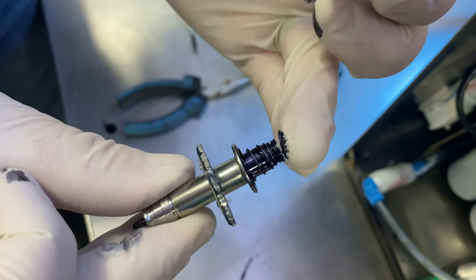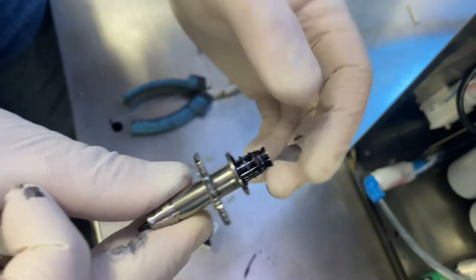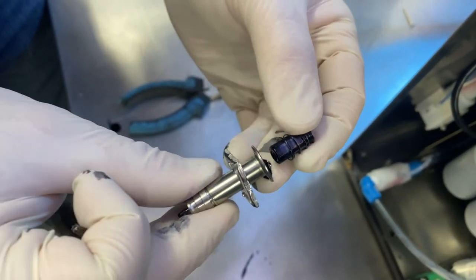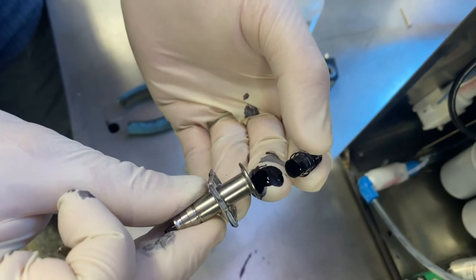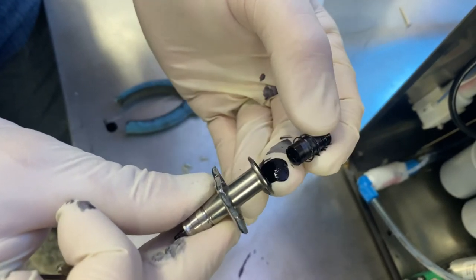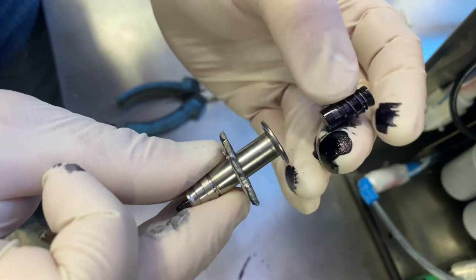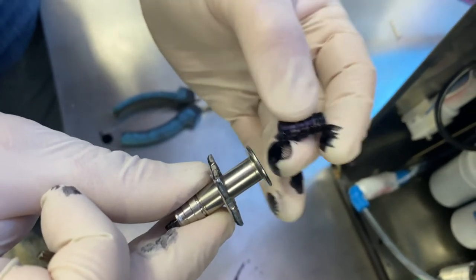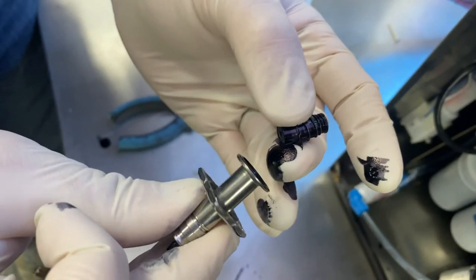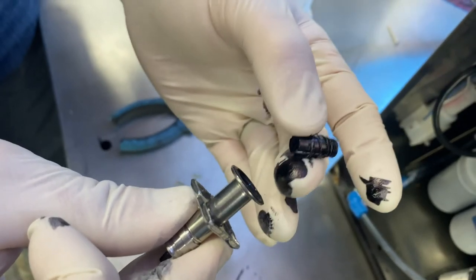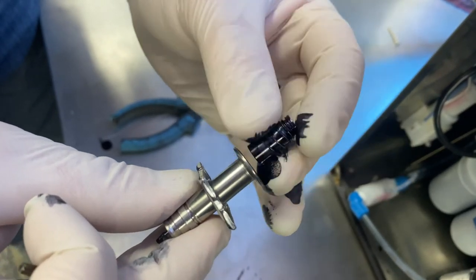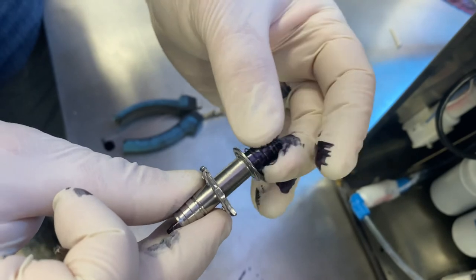If it's not moving freely, what we need to do is clean this up, and you can actually take this plunger out. You'll see there's a little bit of ink inside here, but in the scenario where this was stuck or the spring is stuck, we just need to clean all this up. If there's dried up ink, we need to get that removed, make sure everything's nice and clean. We'll put it back together and we should be good to go.